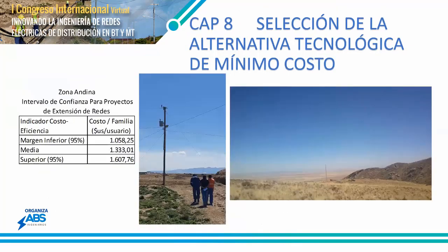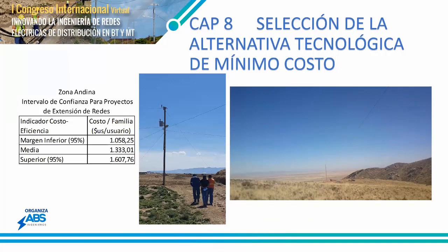Tenemos algunos indicadores de costo-eficiencia para la elaboración de proyectos de electrificación rural. Por ejemplo, en el área andina o el altiplano, se puede usar un margen inferior al 95% con un intervalo de costo-beneficio por familia de mil dólares. Lo que hace el proyectista es sacar el número de usuarios, la cantidad de materiales y cuánto le cuesta por kilómetro. Si el costo por usuario está en el margen superior de mil seiscientos dólares, el proyecto es viable — considerando la topología de la comunidad o del área de influencia para la zona andina.